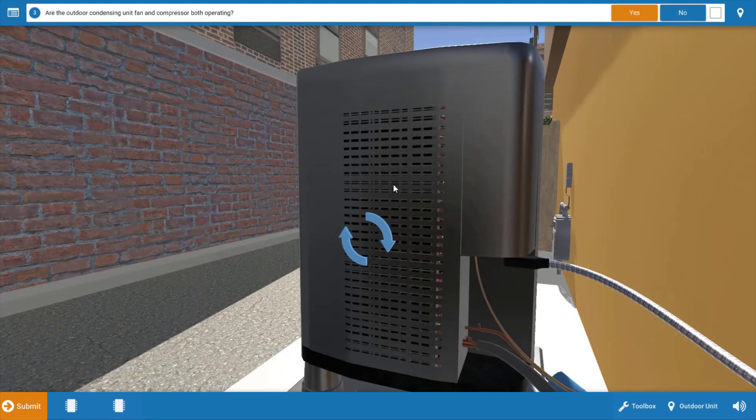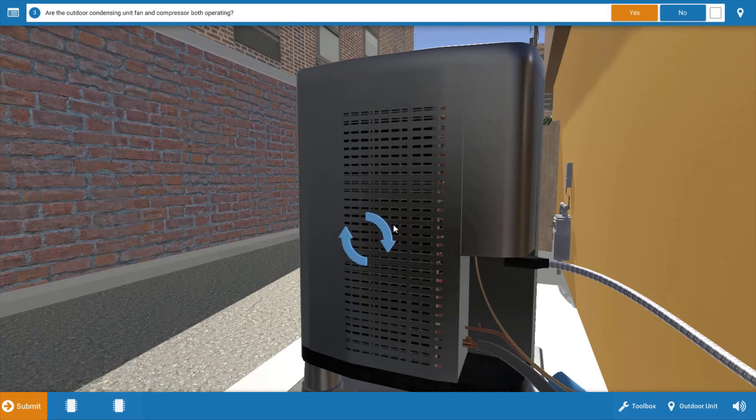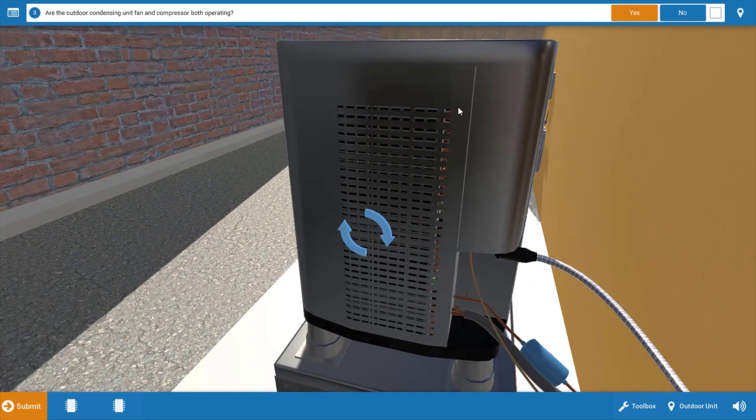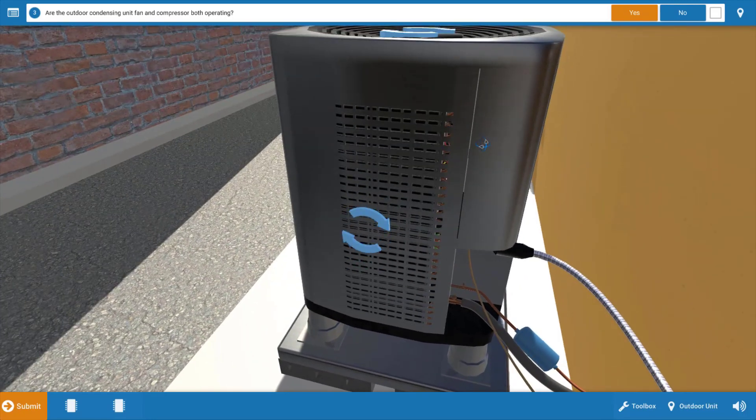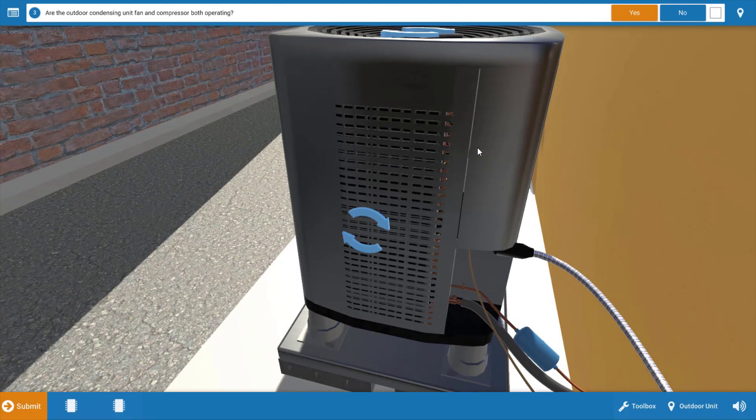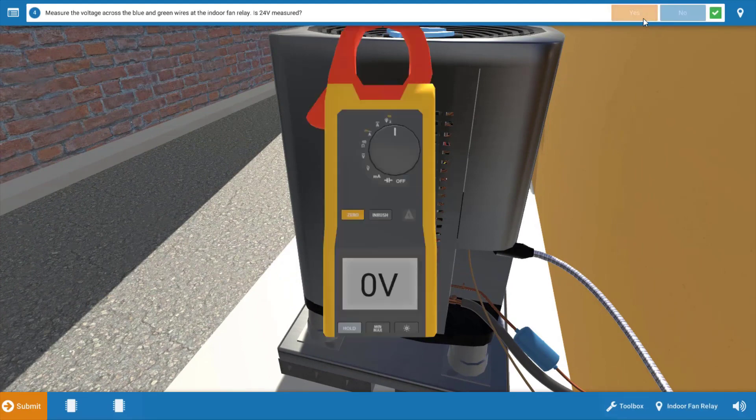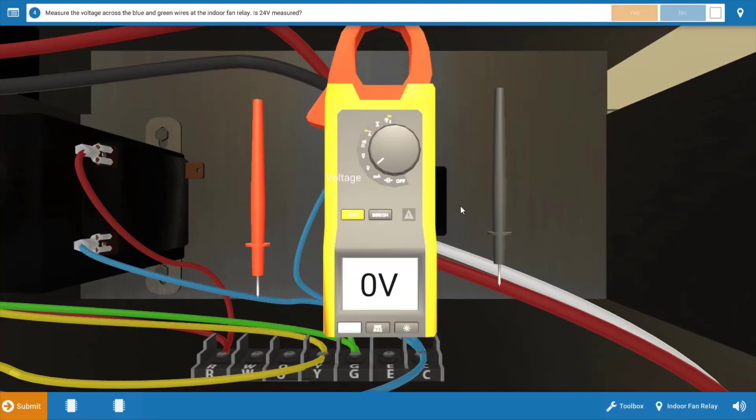We go to the outdoor unit, we can see that both the compressor as well as the condenser fan motor are running. The arrows are spinning, both of those are running, so we're going to click yes there. So the source of our problem here is, in fact, the indoor fan motor.